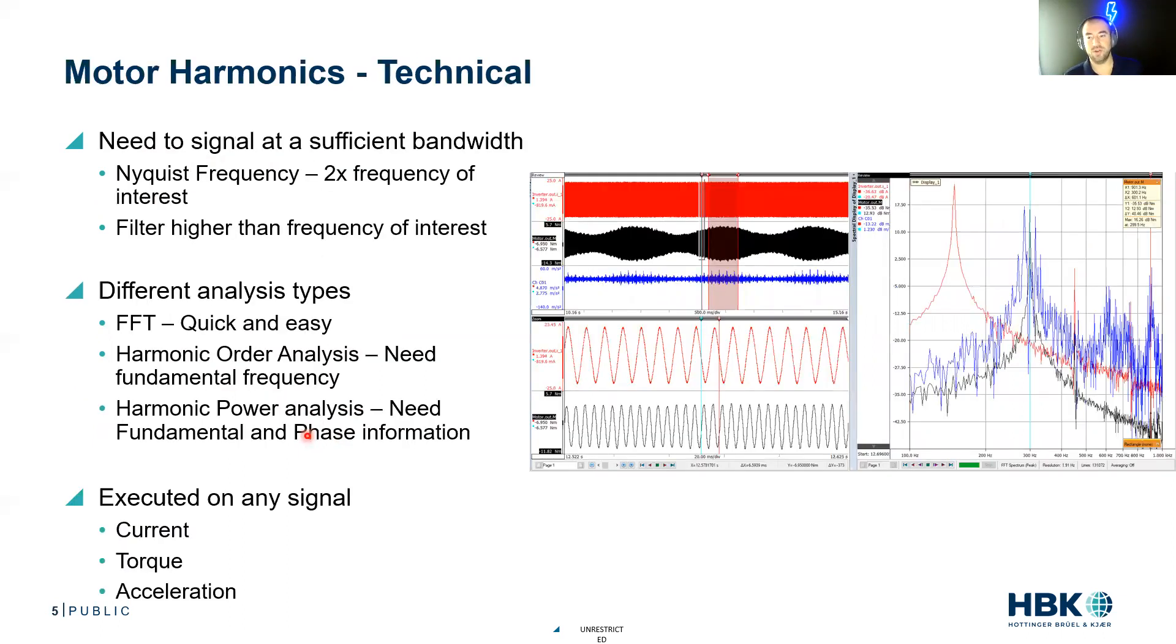A little technical dive into the harmonics. When we're measuring harmonic content, we need to signal at a sufficient bandwidth. We need to measure the signal at a high enough frequency so that we can understand the content we're interested in. Now the Nyquist frequency, everybody learns this in school, it's two times the frequency of interest. We really want to sample probably 20 times higher than our frequency of interest.